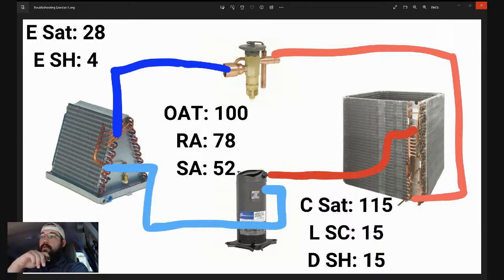We checked both of those. So you take off the evaporator panel. Obviously we've shut the system down at this point. We inspect the evaporator coil. It's mounted properly, no major issues, no major flap issues. So as far as you can tell, without tearing the whole thing apart, the evaporator is not bypassing in any way. Now, another way we could verify the bypassing is our external static. Would we have that high of an external static if we were bypassing our coil and just flowing around it? Wouldn't that remove restriction, which would ultimately lower our external static? Just something to think on.